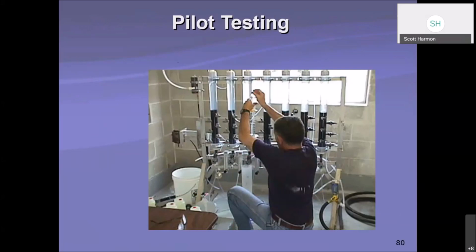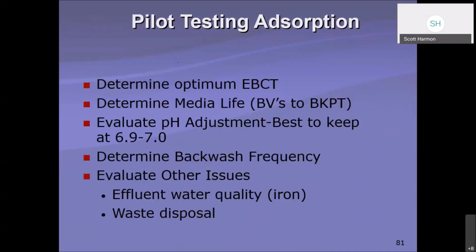Pilot testing with any of these processes has been key in the past, and I'm sure if you're building a new facility, pilot testing will be key in the future for them. So there's some different pilot tests that are out on the market, and these are some of the things that people evaluate to be able to build a full-scale plant. So you determine what the optimum bed size is, your media life, your best adjustments for pH, your backwash frequency if you're not using throwaway media.